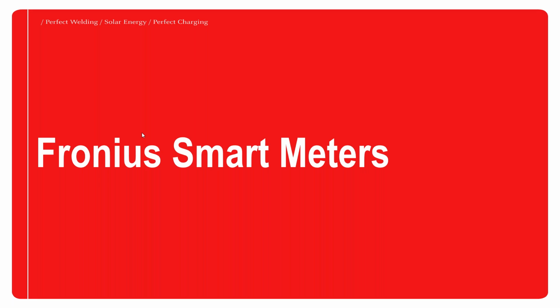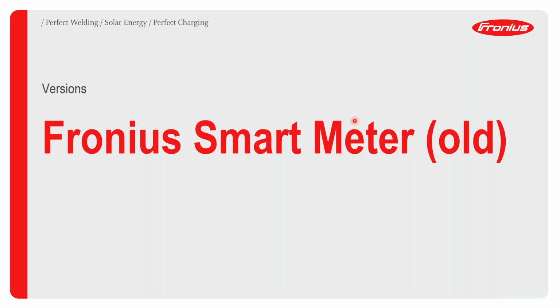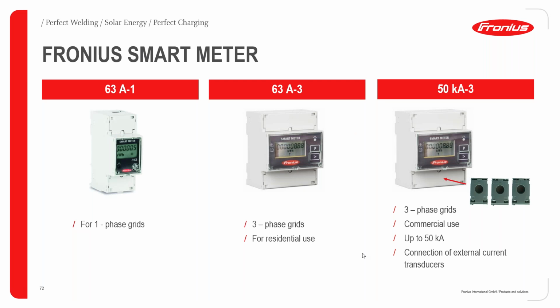Moving on now to the Fronius smart meters. Let's give you a bit of info about the available smart meters. We have the old version smart meters, and the smart meters, of course, are used in conjunction with all grid-tied installations for a number of things that we are going to look at later. In a nutshell, we have 2 variations of smart meters. We have the single phase and 3-phase residential smart meters, as we can see here, so 63 amp single and 3-phase meters. And also we have an old version of 50 kilo amp 3-phase commercial meter.